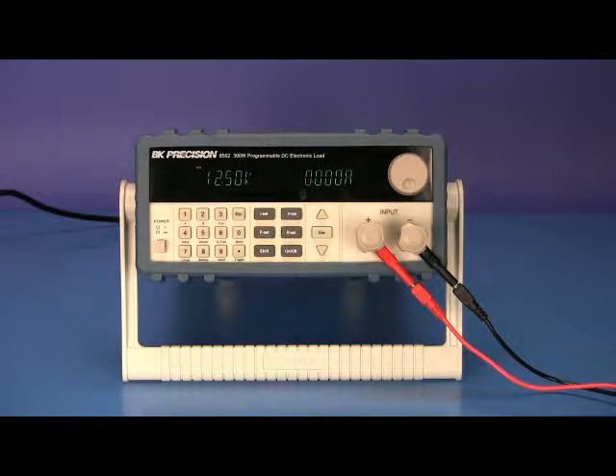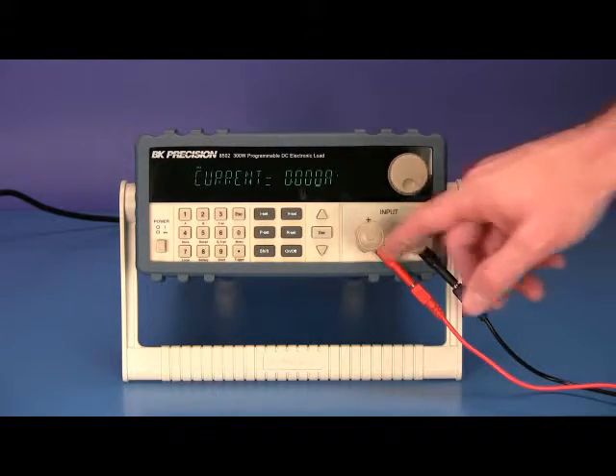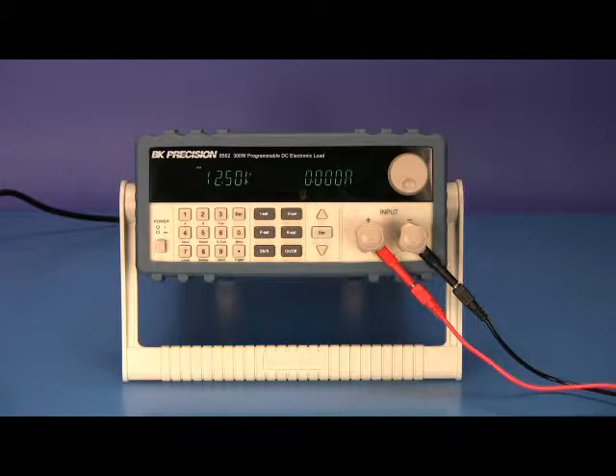To run a battery test, press the ISET button. Using the numeric keypad, enter the constant current value you wish to draw from the battery during the test, followed by pressing the enter button.